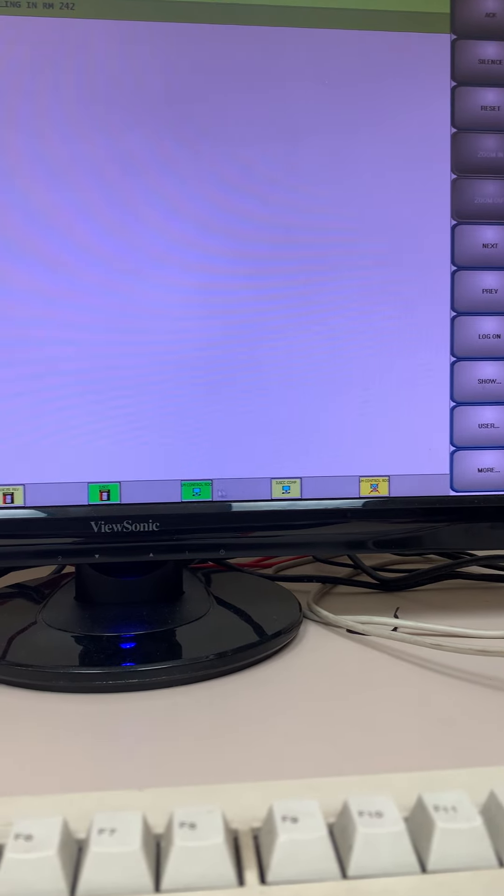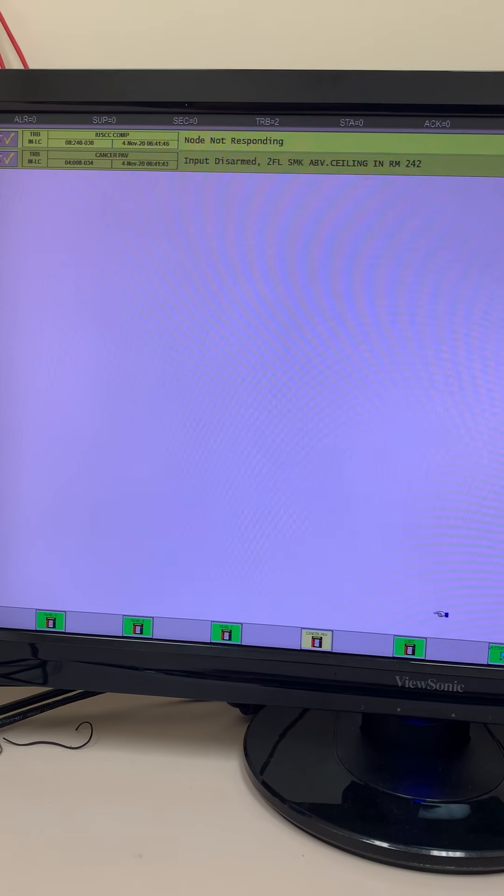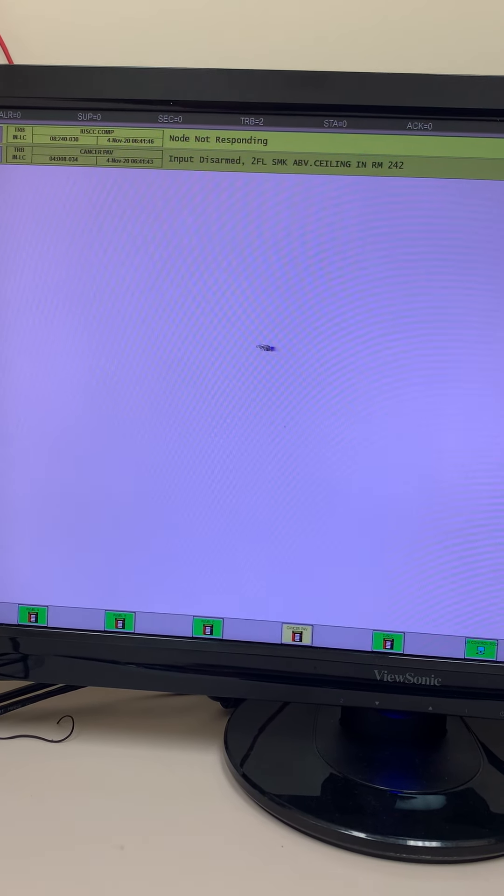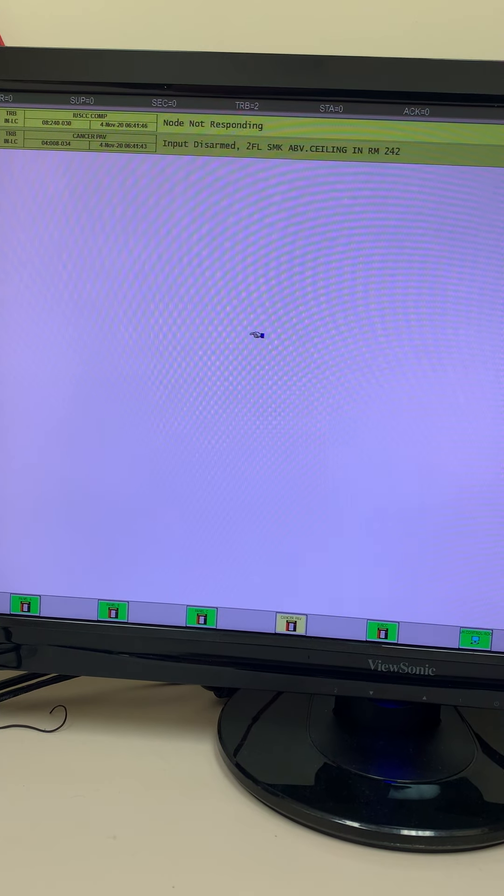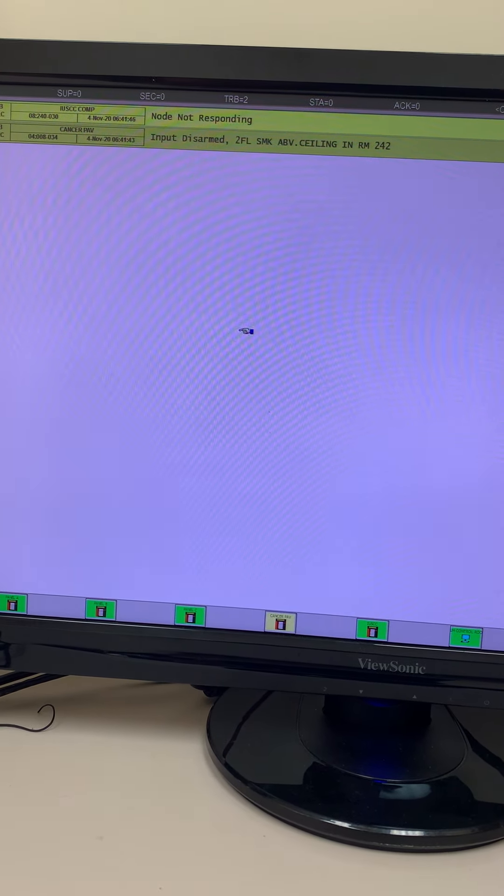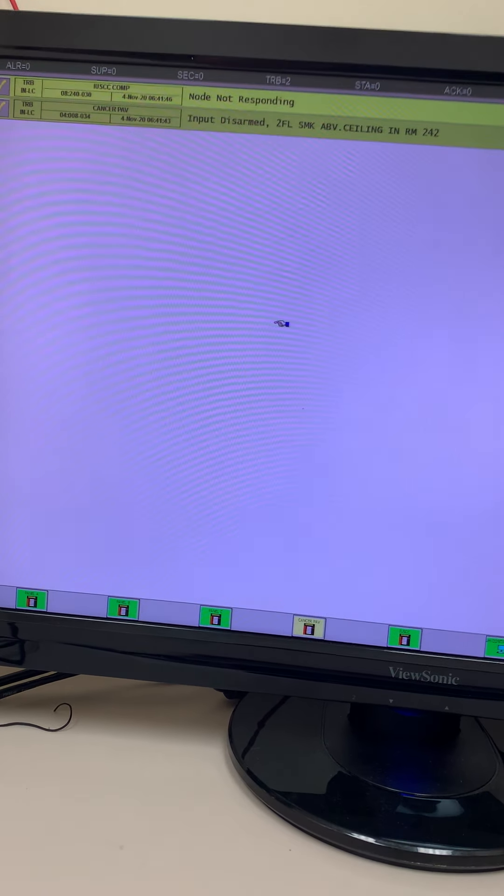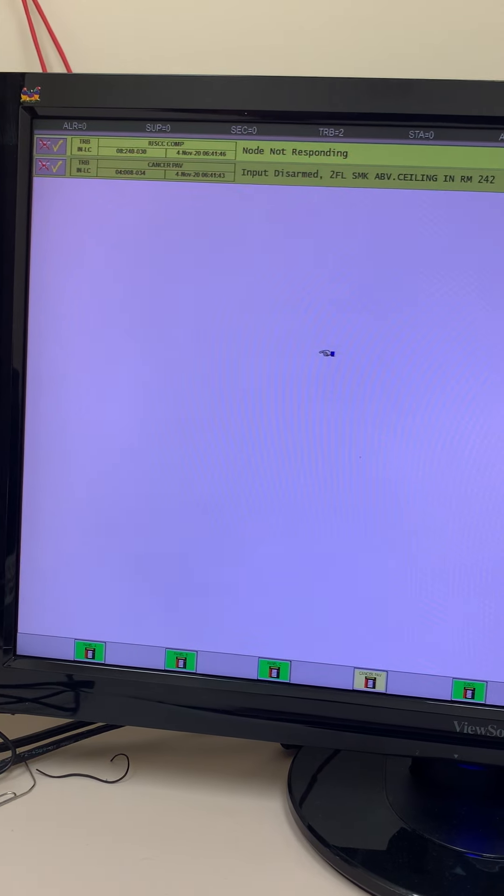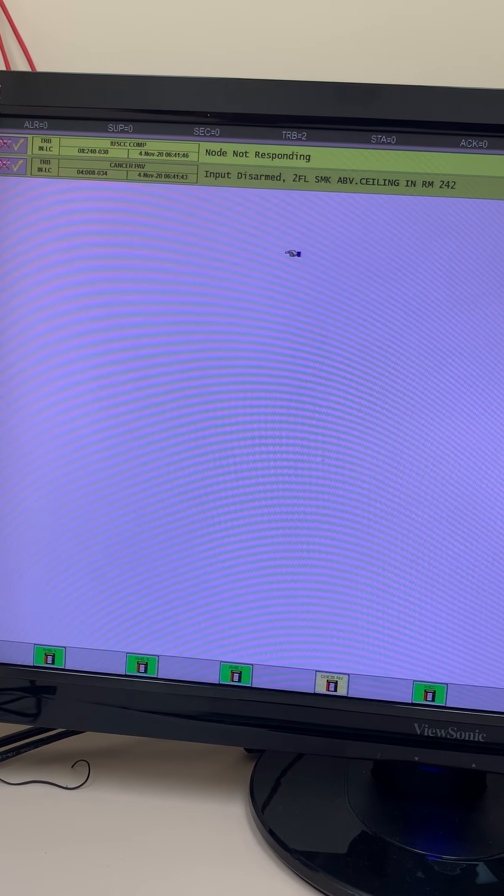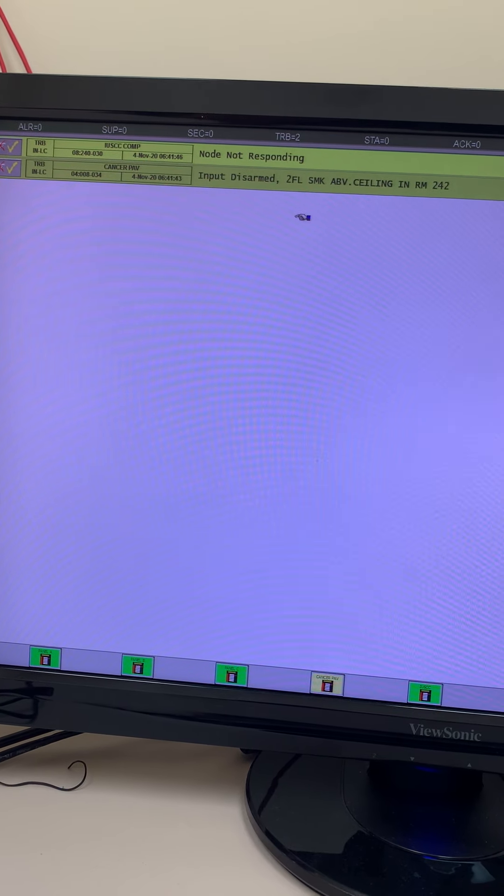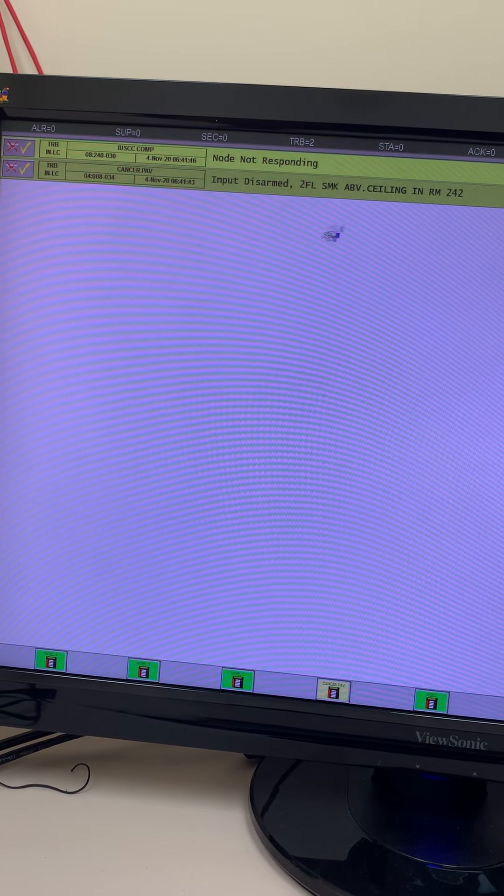Most of these are lit up in green, but you could see we have the Cancer Pavilion that is lit up in yellow and this workstation showing up in yellow as well. The reason for that is we've got a couple of troubles. This node not responding is actually talking about this computer right here, and we really don't know why that is because this computer works absolutely fine. We also have one device that is disarmed in the Cancer Pavilion, a second floor smoke detector above ceiling in room 242.